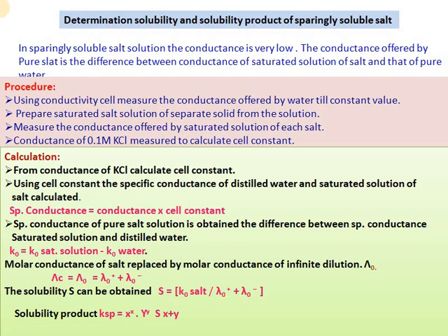Firstly, using the conductivity cell, we measure the conductance offered by the pure water till a constant value.